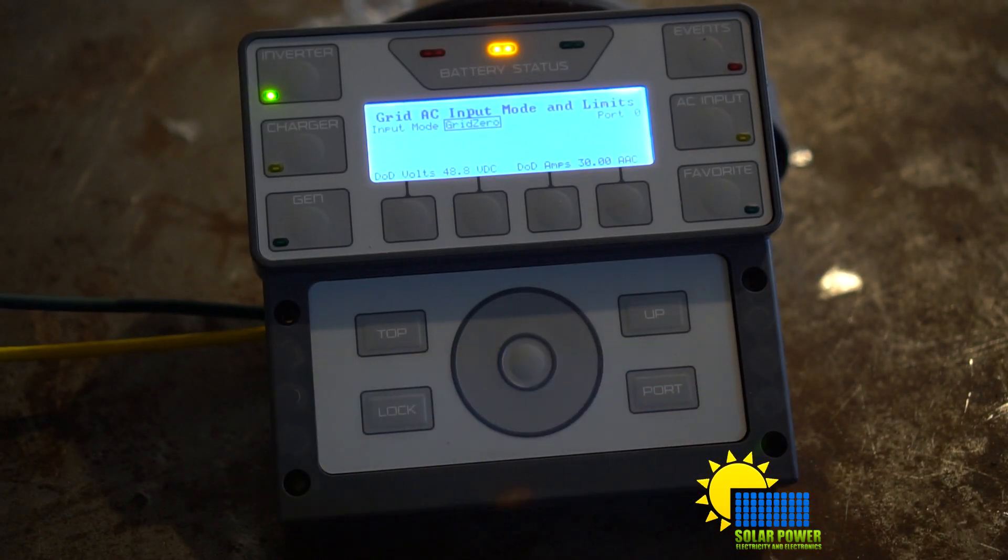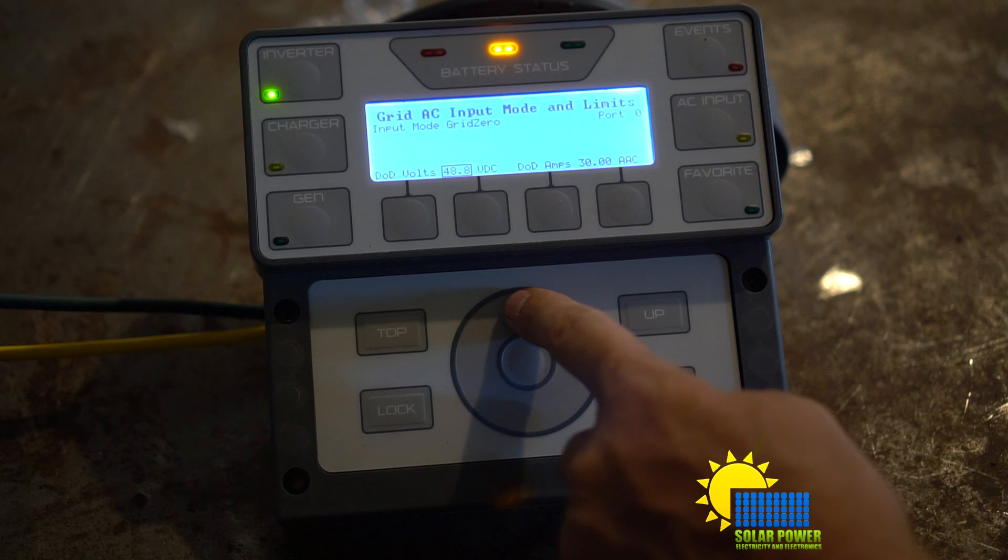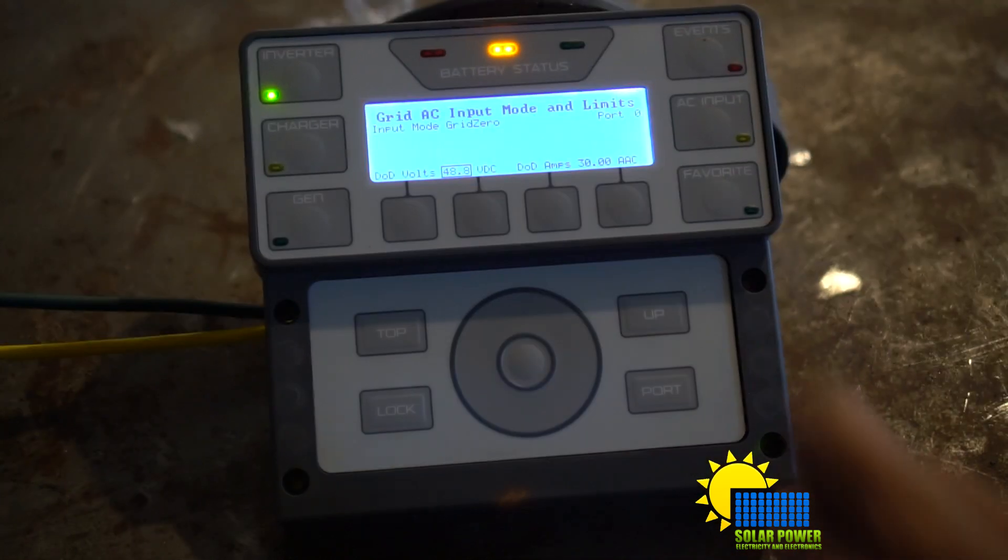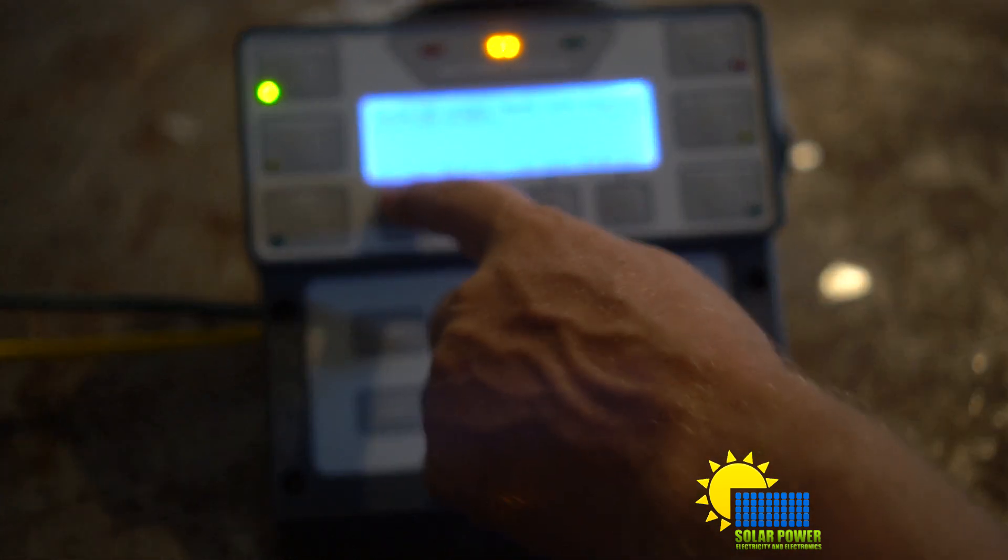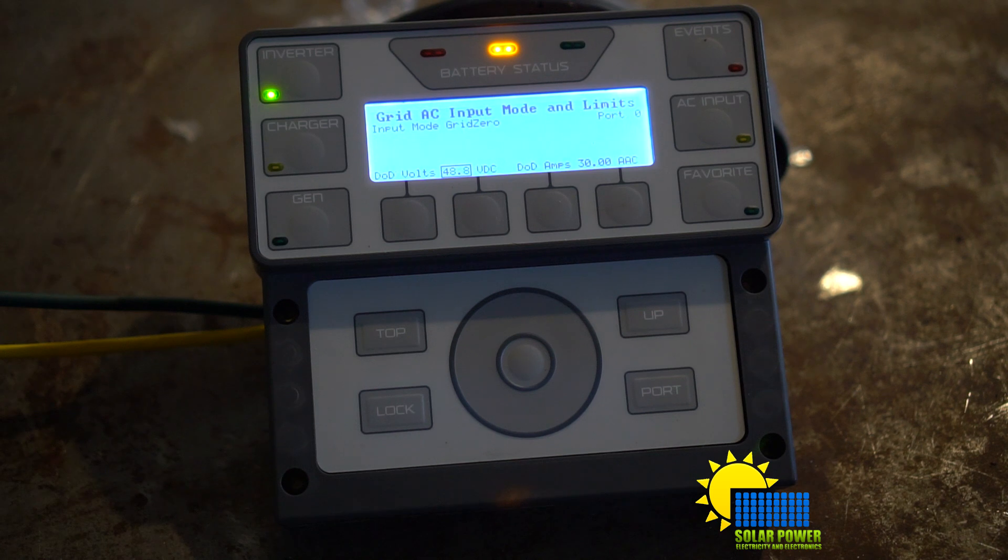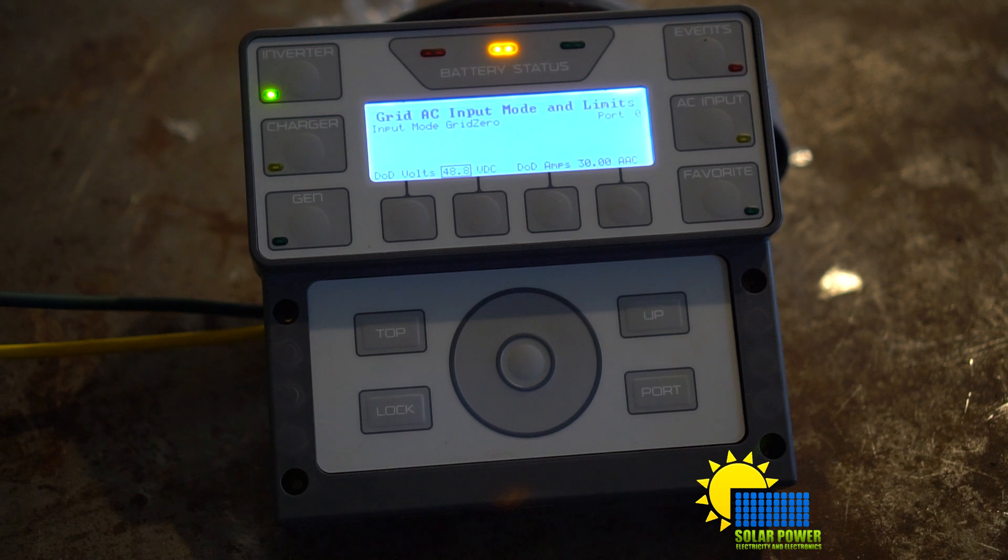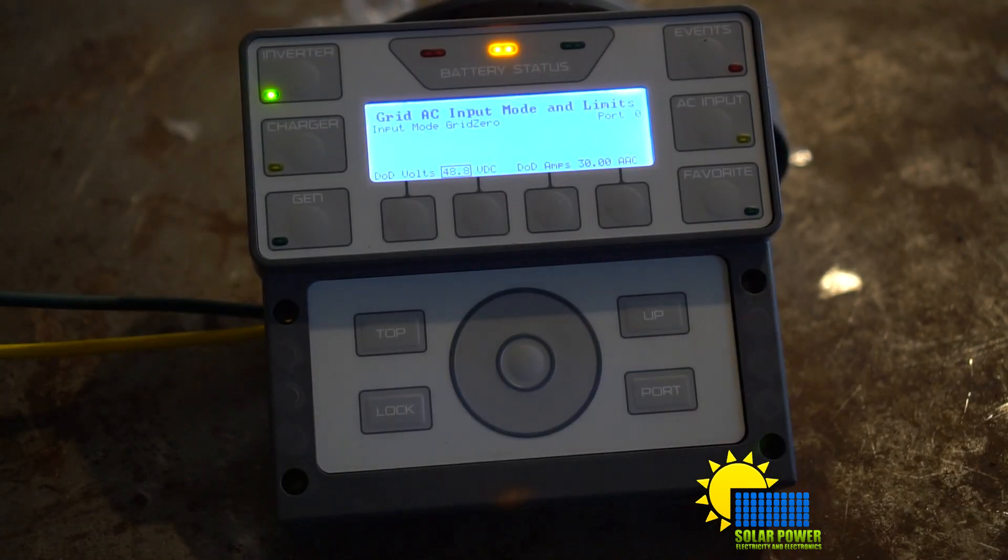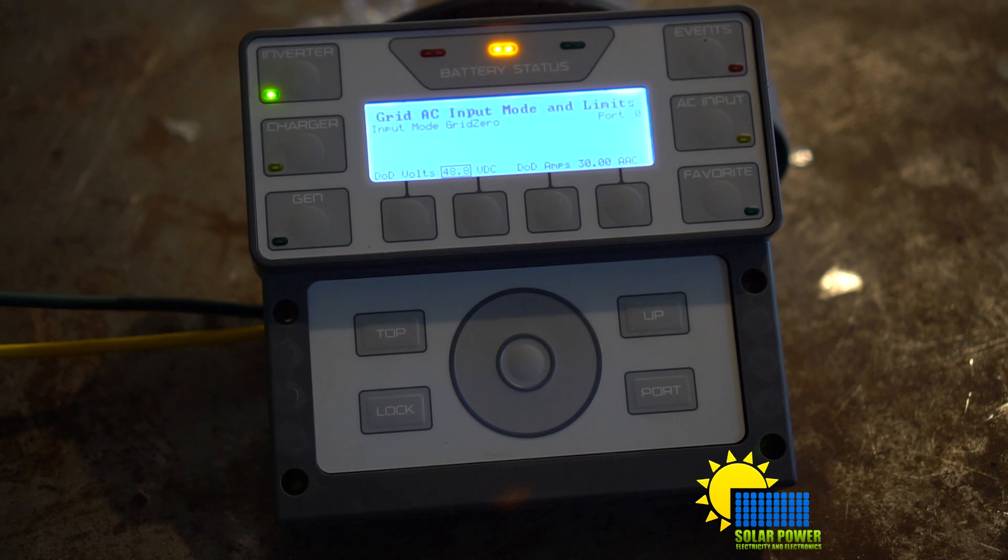And then you're going to move over to DOD volts. That means depth of discharge volts. 48.8 is what I have mine set to, and I have a clever way to exhaust all my electrical power that I'm gaining during the day. That's a good thing, so I'll explain that to you in just a moment. I set it to 48.8 for my specifications. I can go a little higher but I'm not going to. This is high enough.